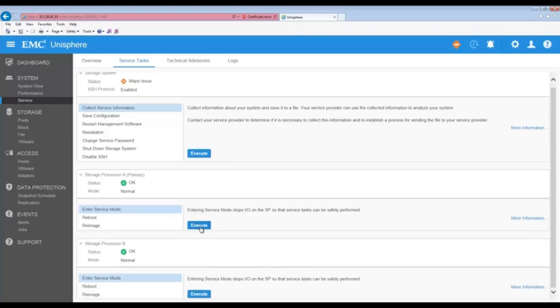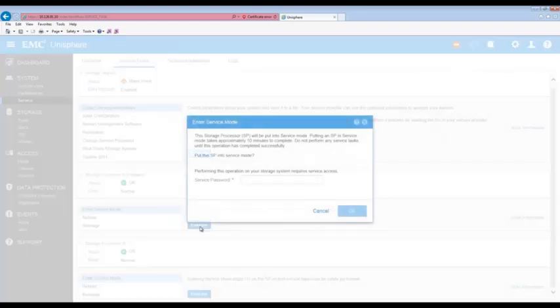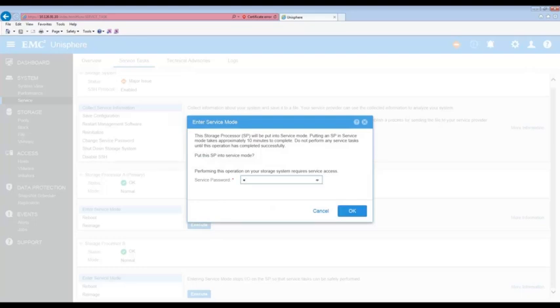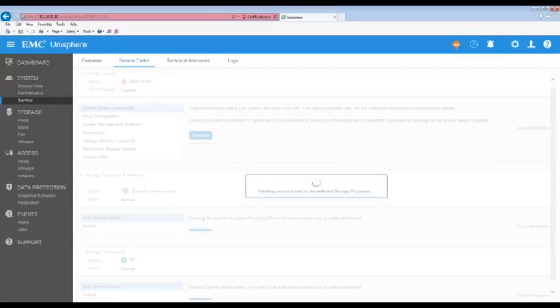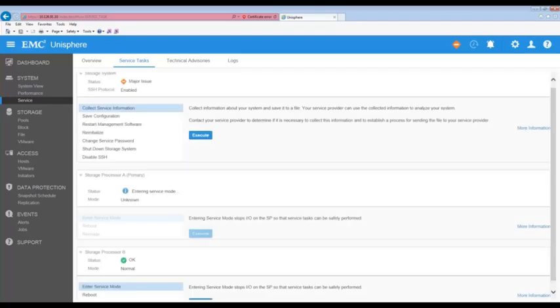When prompted, enter the service password. Entering Service Mode stops IO on the SP so that it can be safely performed. Wait until the SP fault LED is flashing alternating amber and blue before continuing to the next task.